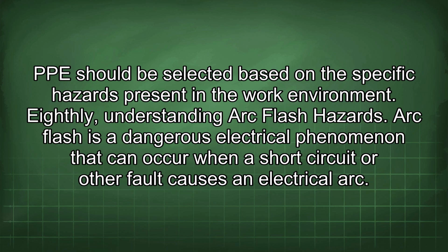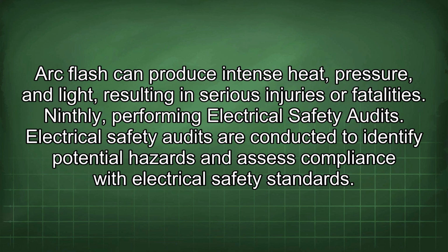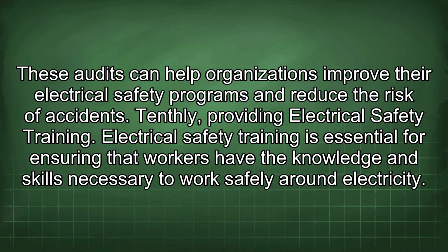Eighthly, understanding arc flash hazards. Arc flash is a dangerous electrical phenomenon that can occur when a short circuit or other fault causes an electrical arc. Arc flash can produce intense heat, pressure, and light, resulting in serious injuries or fatalities. Ninthly, performing electrical safety audits. Electrical safety audits are conducted to identify potential hazards and assess compliance with electrical safety standards. These audits can help organizations improve their electrical safety programs and reduce the risk of accidents.